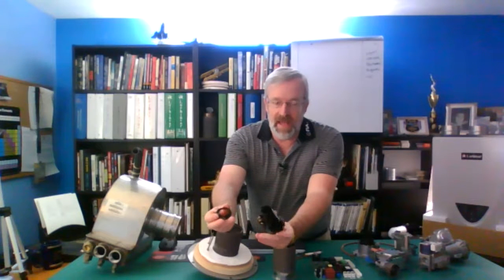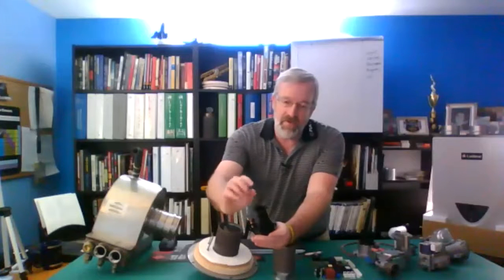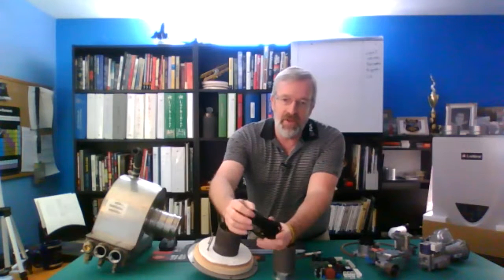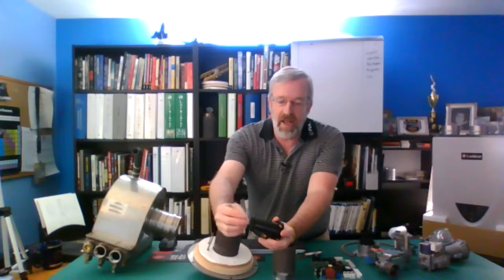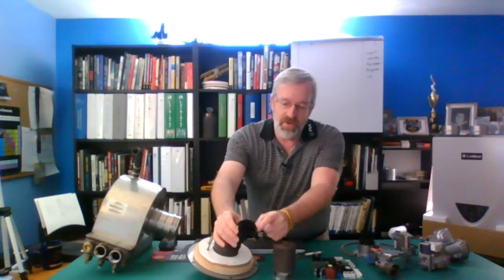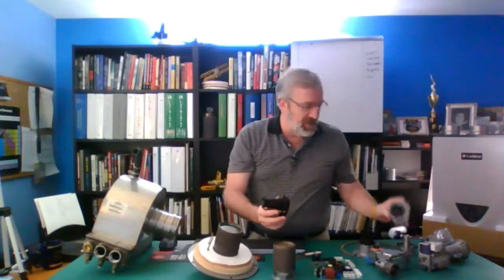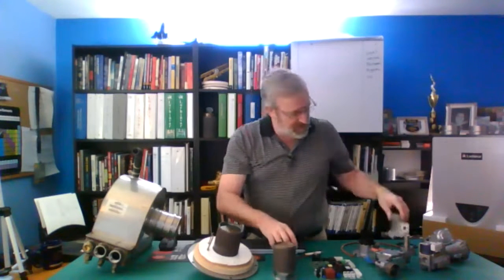On the end, I've got this end cap. When that cap fits on, it actually creates an opening right in here. That's the orifice. As the air moves across there and draws through, it creates suction on the outside here, and that suction translates through into here. And this is where the real adjustment point is. So this all inserts in here. As I pull the gas in, the gas is going to come in here, on the outer part of that center orifice, and then gets dumped in, where it creates a gas-air mixture. Then it's going to push it through, take it into our fan and into our burner.